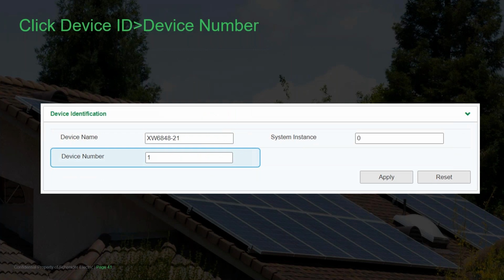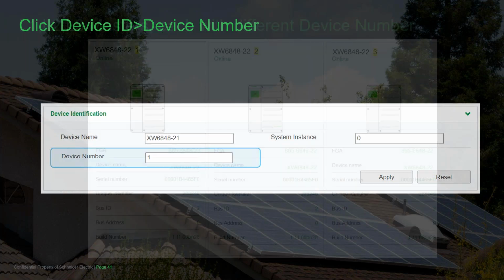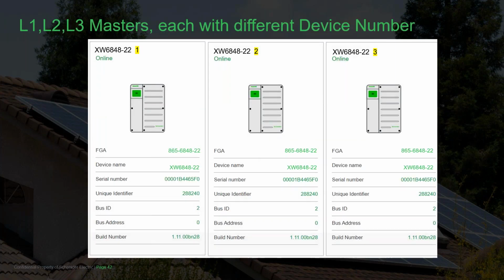Next, navigate to the device identification section and select device number 1. Numbering is irrelevant, provided each XW Pro has a different device number, and then click Apply. Once you've programmed inverter number 1 as 3-phase L1 master, inverter number 2 as 3-phase L2 master, and inverter number 3 as 3-phase L3 master, with each having a different device number, it's time to set the system up for how you intend to use it.